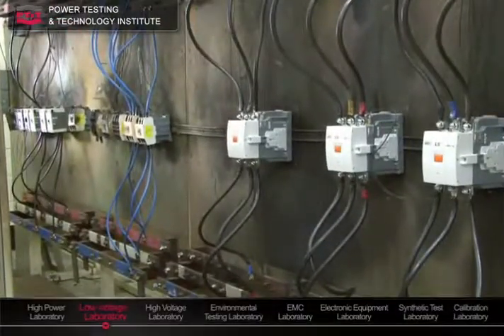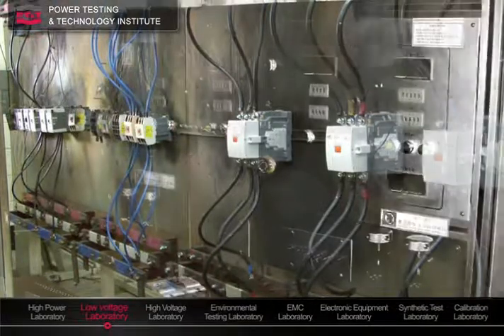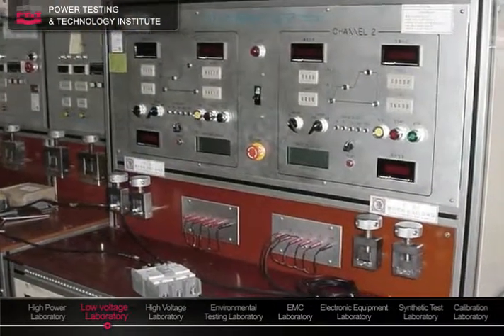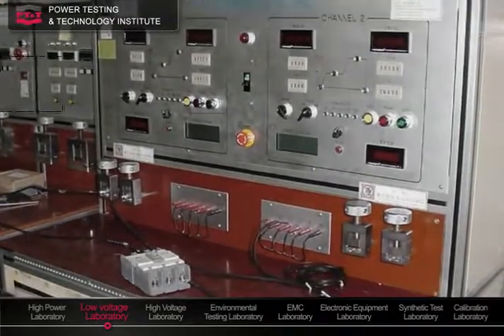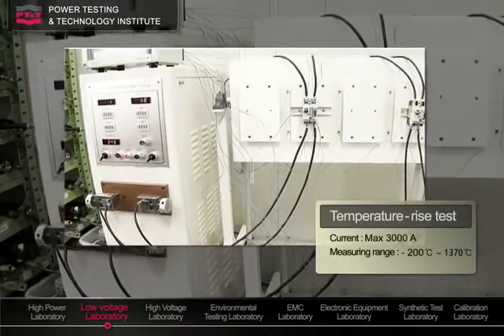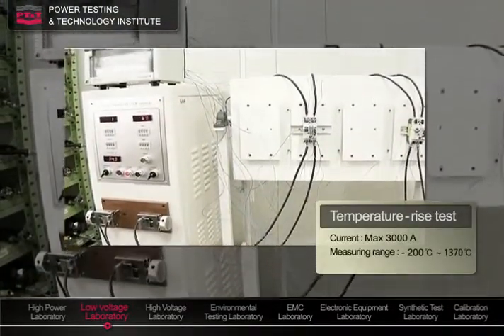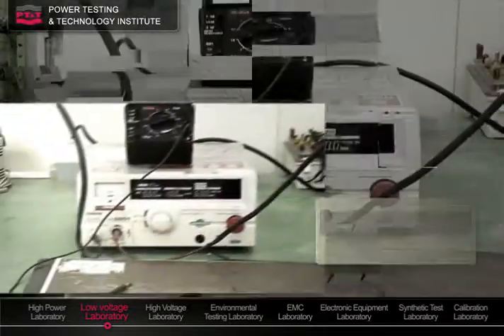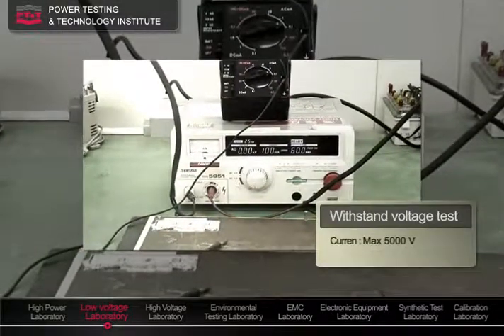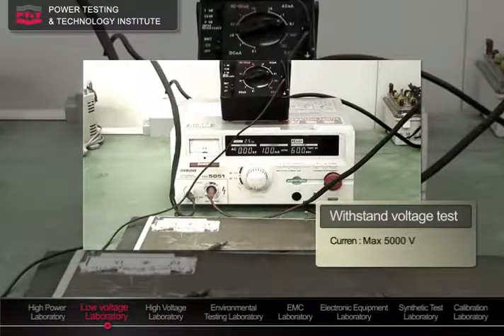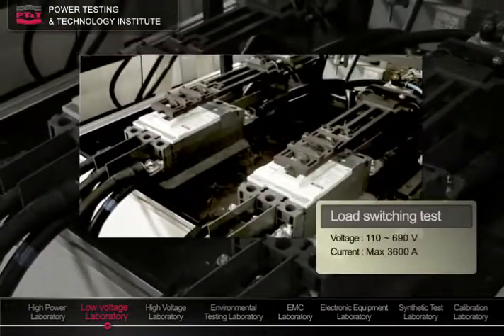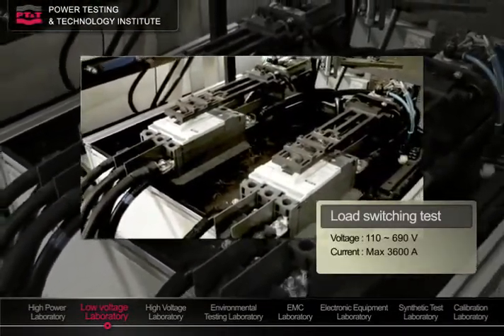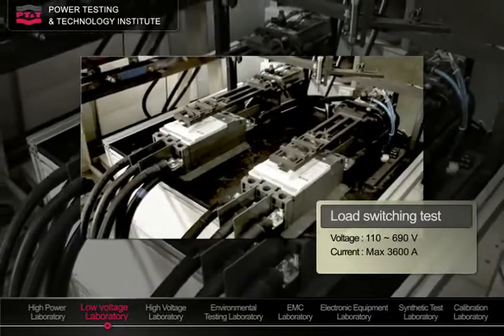Low voltage laboratory is for the electrical performance tests of molded case circuit breakers and magnetic switches under 1000 volts. Current carrying capacity is verified by temperature rise tests. Dielectric insulation is verified by withstand voltage tests, and load current switching performance tests are also performed here.